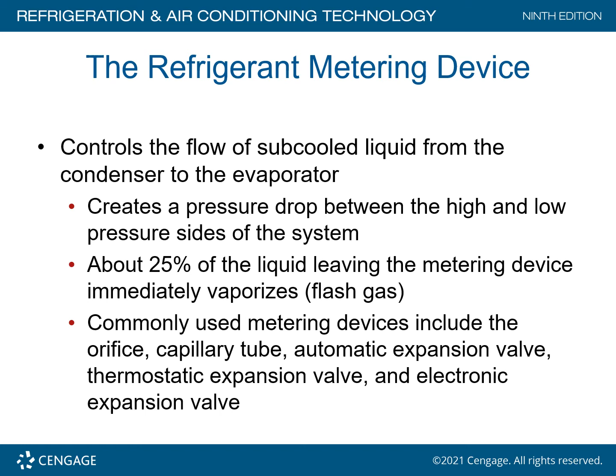Okay, the orifice. Old air conditioning systems as well as some refrigeration systems. Notice that coming through here we have 100% subcooled liquid. We're at 446 psig. Now we put in an orifice right here. Now with that orifice, look what happens. Now we have a partial liquid, 75%, and a partial vapor, 25%.